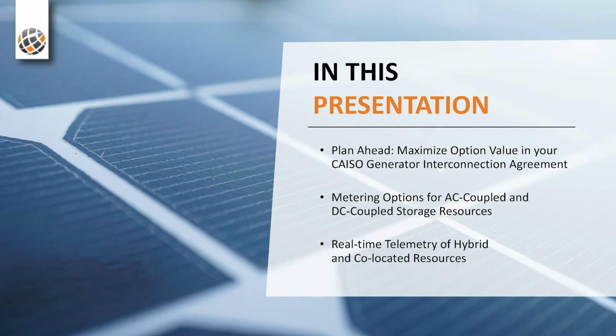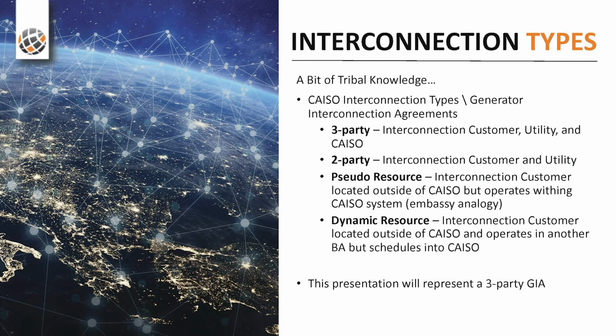Just a bit of tribal knowledge inside interconnection agreements. Typically there are 3-party and 2-party agreements. The 3-party agreements are the interconnection customer, the utility that you're connecting with inside the ISO's BA, and the ISO itself. A 2-party agreement is typically the utility you're connecting with and the interconnection customer themselves, which is typically a WDAT or Rule 21. There are two other ways to interconnect or become a participant.